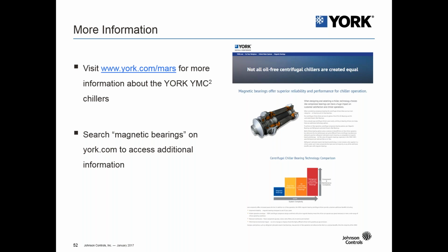All right. We have a question here asking if the YMC squared chiller can work with chilled water supply temperature at 28.5 degrees. I think we're asking in terms of a glycol-based system, if glycol is a possibility and that kind of extended capability. Yeah, so the YMC squared is able to handle leaving fluid temperatures with glycol or brine down to 10 degrees Fahrenheit.